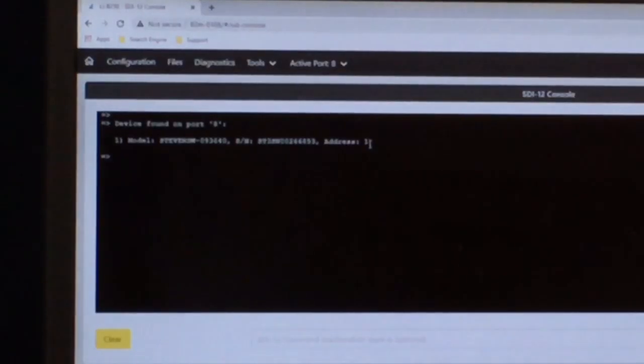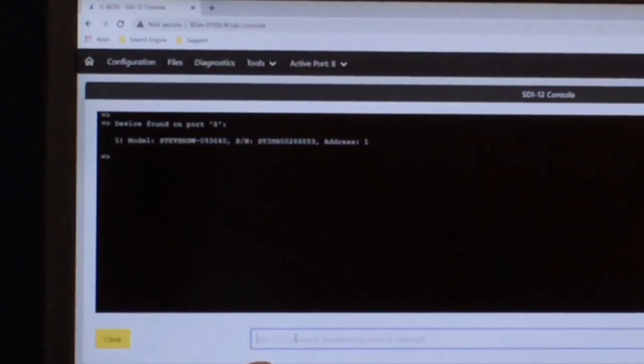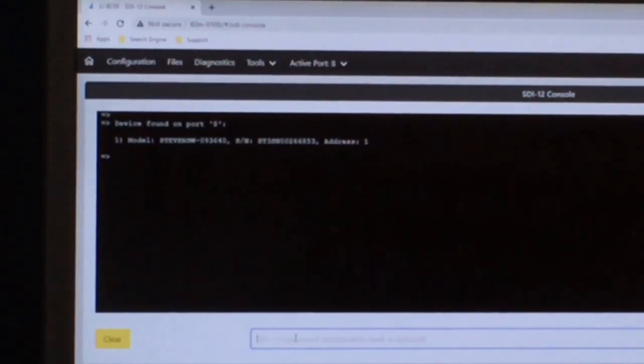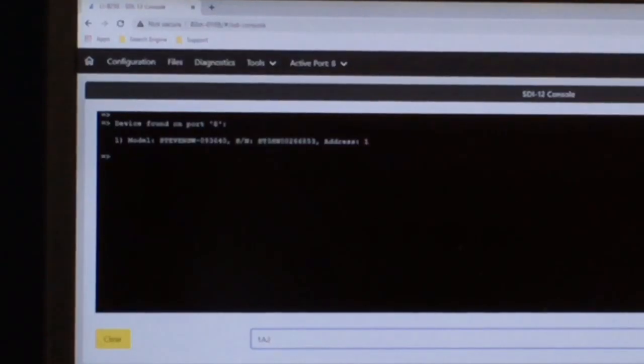Now I want to check what address the sensor currently has. To do that, I can press Query All. You can see currently my SDI-12 sensor has the address of 1. Say I want to change the address, then you need to send a command over here. The command is in the format of one number, the letter A, and a second number. The first number is the current address of your sensor, and the A means address. The second number is the new address you want to assign to the sensor. Then you click Send.